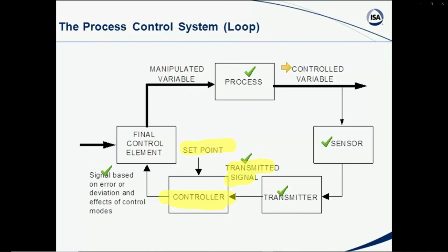the sessions also, out to some final control element, perhaps a control valve, perhaps a variable speed drive, could be some other type of conveyor, starting and stopping a motor, or some type of situation there, but some final control element that varies some manipulated variable, which is an input to the process and does impact or correct for disturbances that we may have in our process. So just briefly, that's our process control system or loop that we will be discussing during the course of these seminars that we'll be conducting.